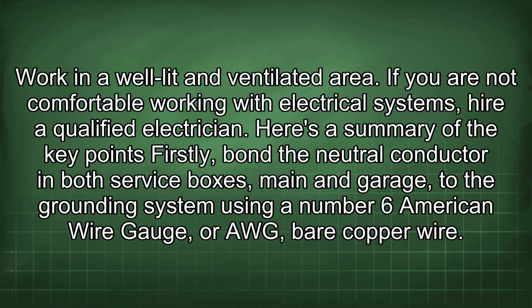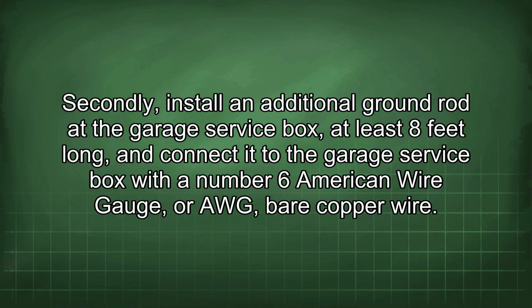Here's a summary of the key points. Firstly, bond the neutral conductor in both service boxes, main and garage, to the grounding system using a number 6 American wire gauge, or AWG, bare copper wire. Secondly, install an additional ground rod at the garage service box, at least 8 feet long, and connect it to the garage service box with a number 6 AWG bare copper wire.